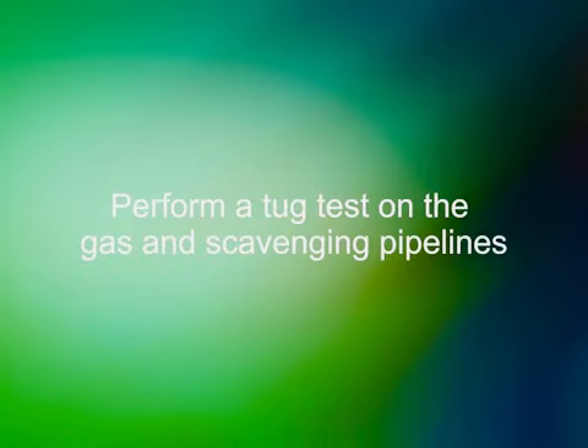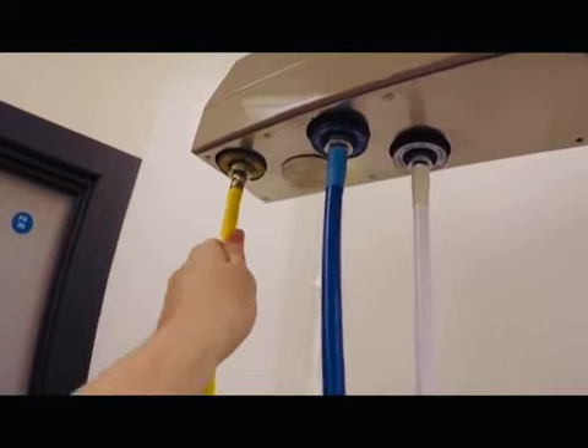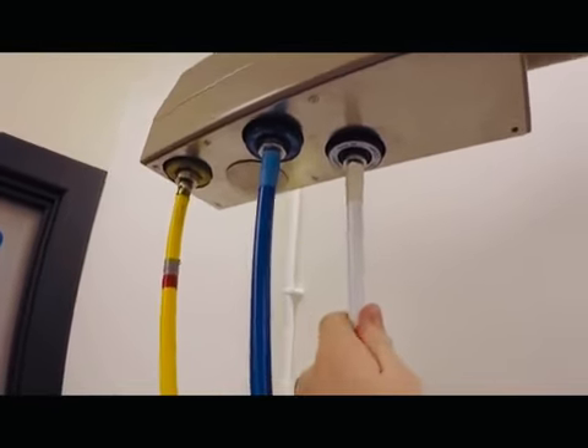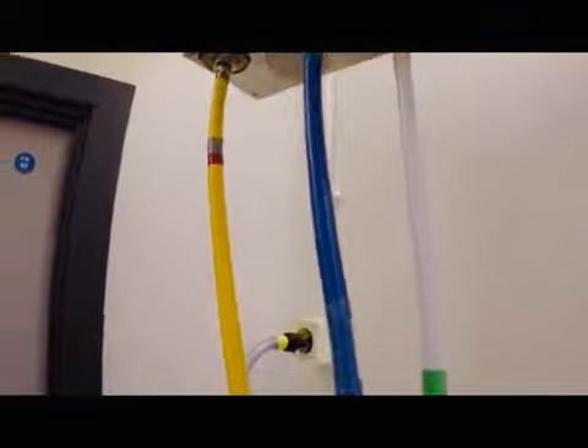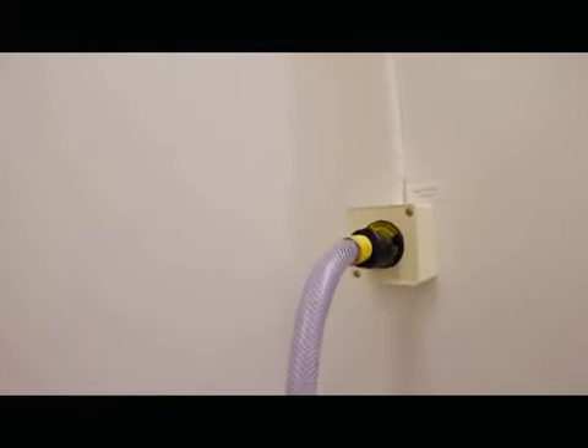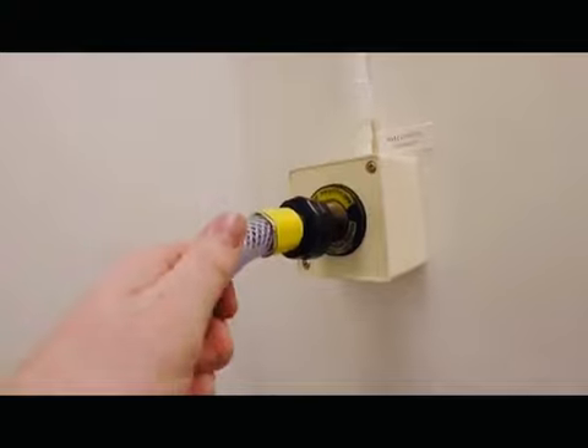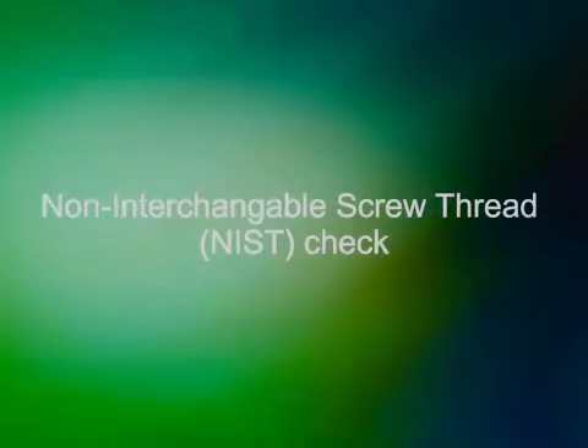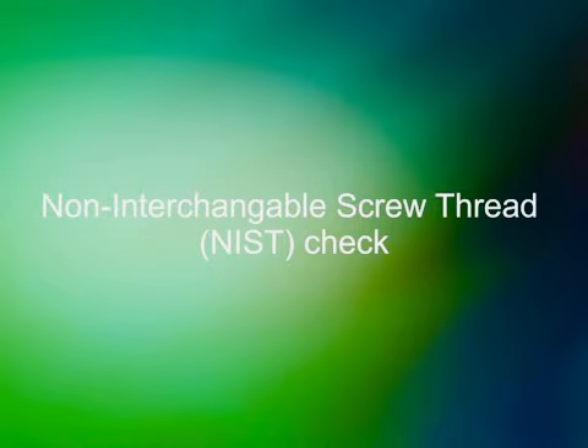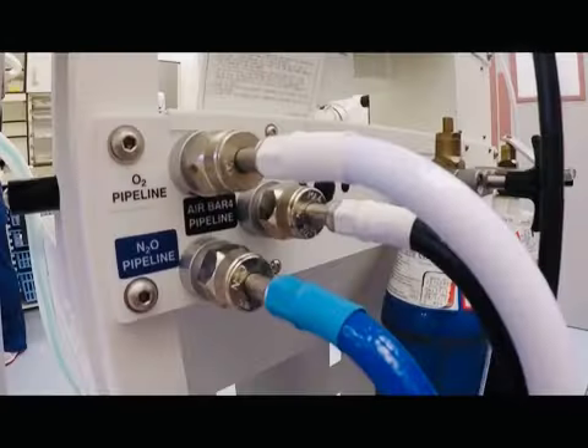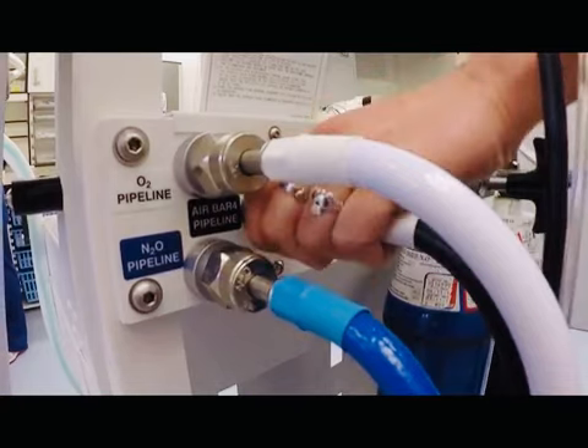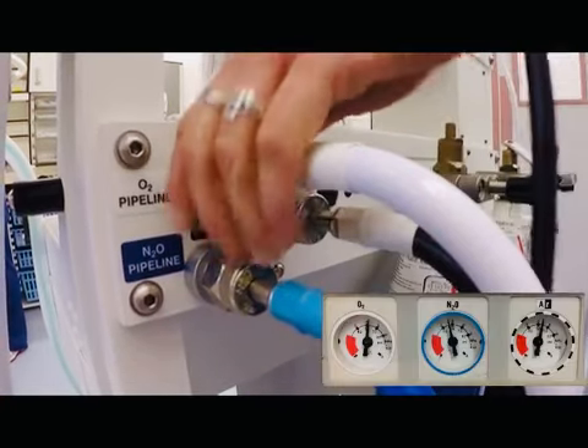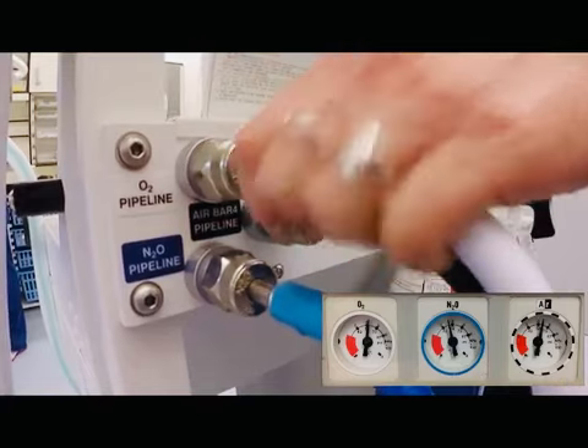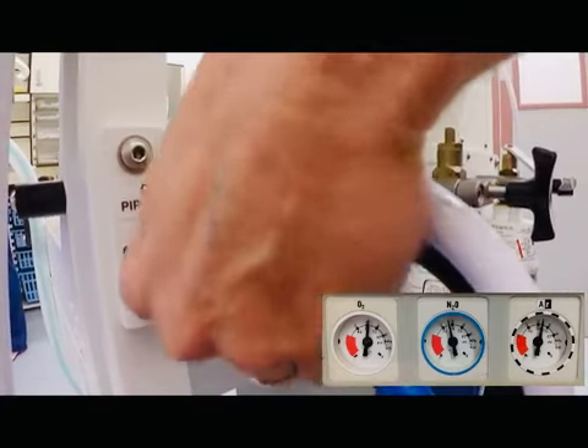Then check that each pipeline is securely attached to its supply using a tug test: suction, oxygen and nitrous oxide, as well as air if being used in the anaesthetic room. Follow these pipelines into the back of the anaesthetic machine and check the non-interchangeable screw thread to ensure secure attachment. The pressure of each pipeline now needs to be checked on the pressure gauges on the front of the machine and should be at 4 bar or 4 times 100 kPa.